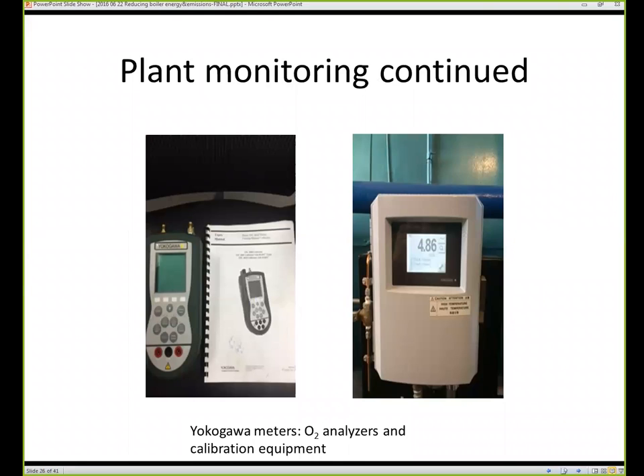Okay, plant monitoring continued. There were a couple of write-ins about what you use. We use Yokogawa, and the particular meter to the left there, we use that. We don't send out any of our gauges to be calibrated. We use that particular deal. And on the safety device testing, we also use that for high and low limit switches to test. To the right is the Yokogawa O2 analyzer, and we do all the calibration on that also.